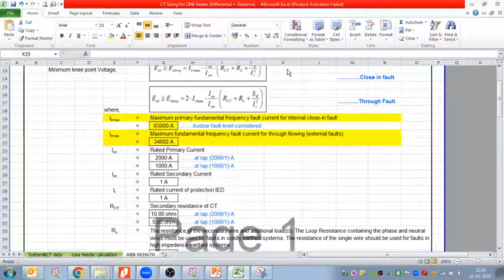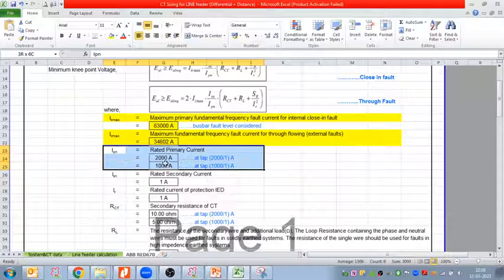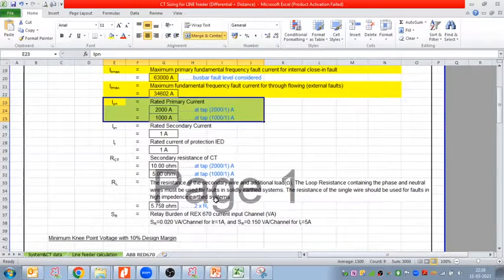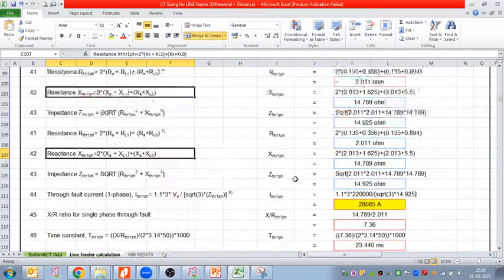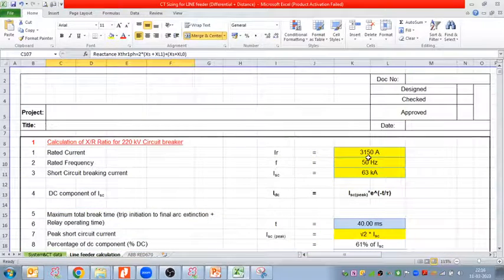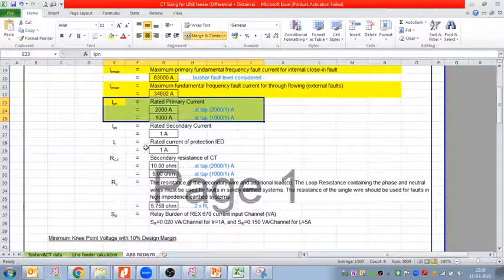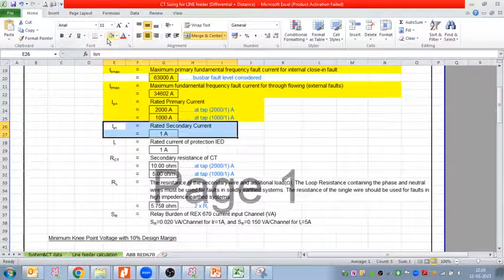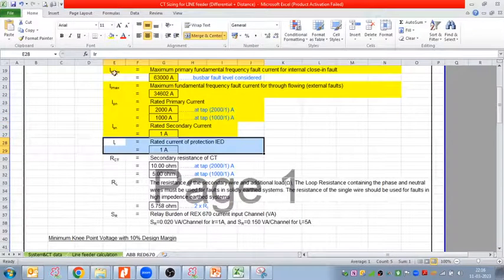CT have two tappings, multi ratio and multi-core. So they have the two tappings, 2000, 1000. So this is my rated primary current of the CT. Right. So I need to correct this value 3150 whatever written. This is my circuit breaker, not the CT. Okay, CT is this much, 2000, 1000. Rated secondary current of the CT is 1 ampere. Rated current of the IED would be 1 ampere, the same as the relay secondary current.